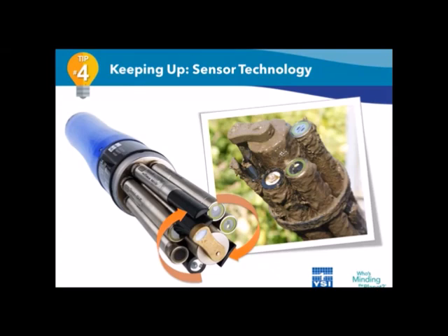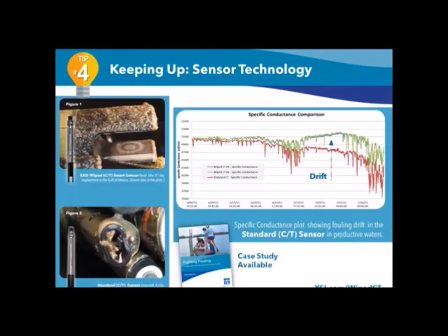And the innovation here is really that the conductivity electrodes I talked about are no longer buried deep within the sensor. They're actually raised up to the same plane as all the other sensor surfaces. And that allows the central wiper that Tiffany discussed to really thoroughly clean the measurement surface. Now, as with all our sensor technology, we put everything through its paces with pretty intense field testing. It's all around the world, and actually that's one of Tiffany's jobs here at YSI. And she helped us develop the case study that you see here on the screen.